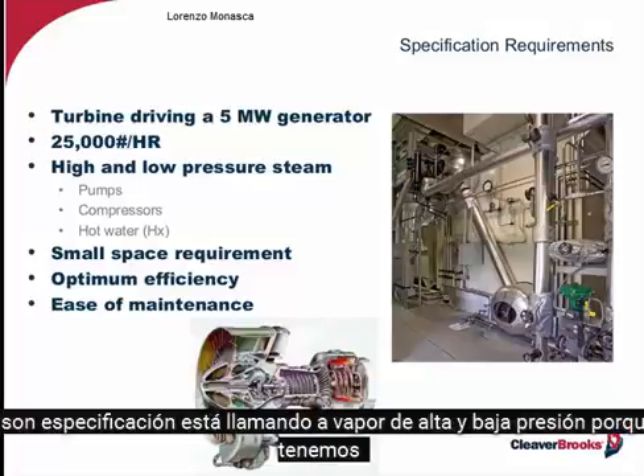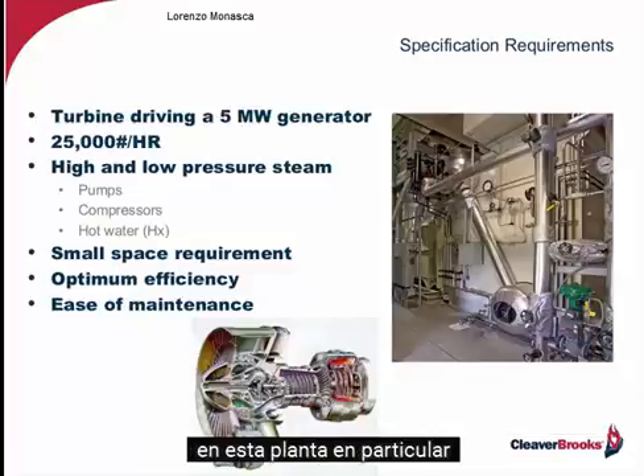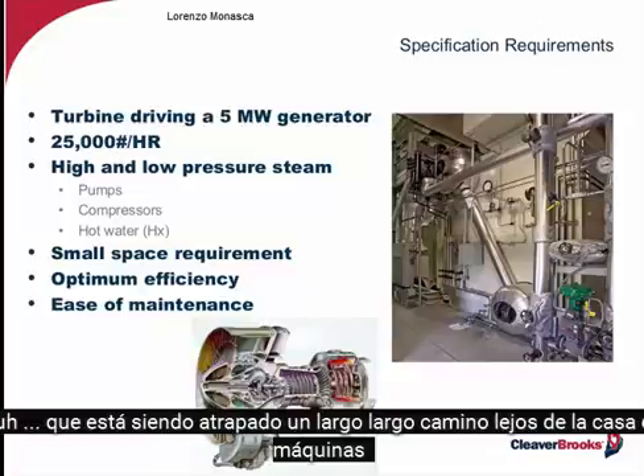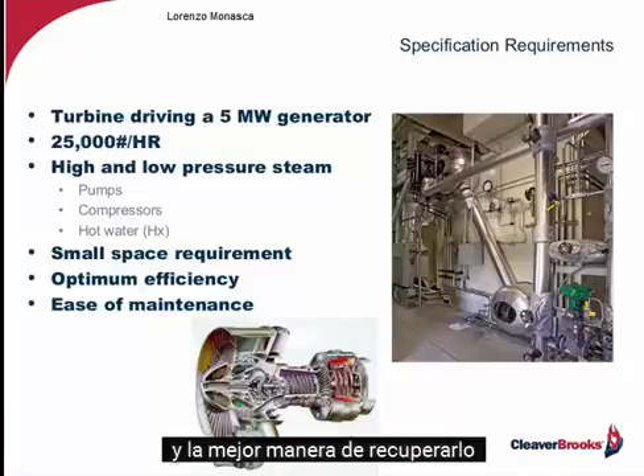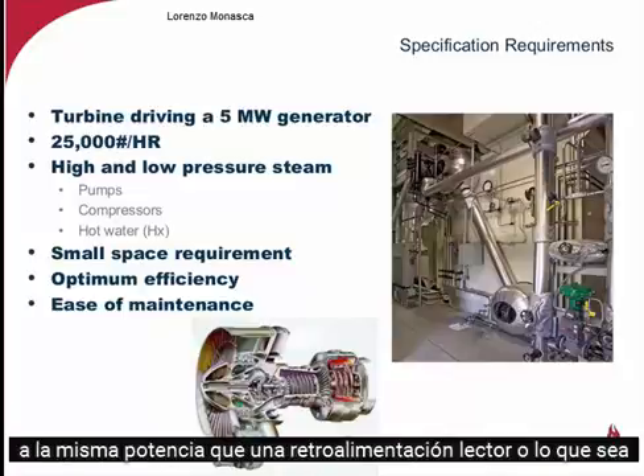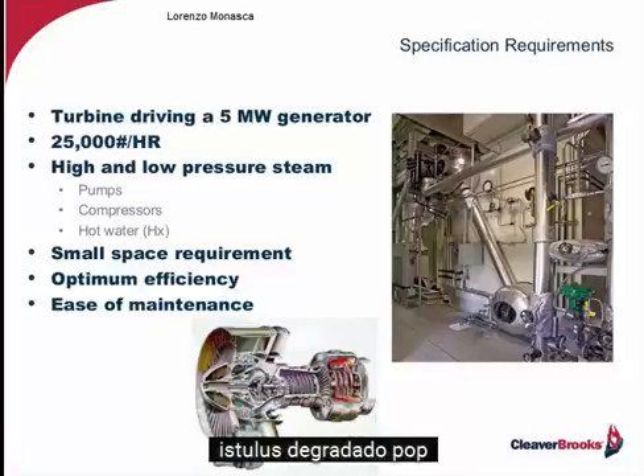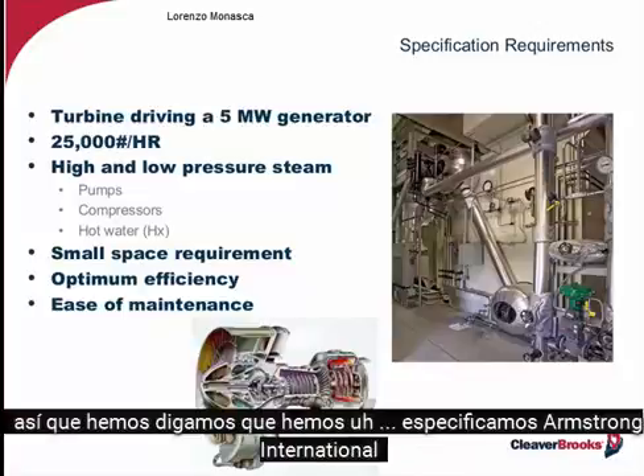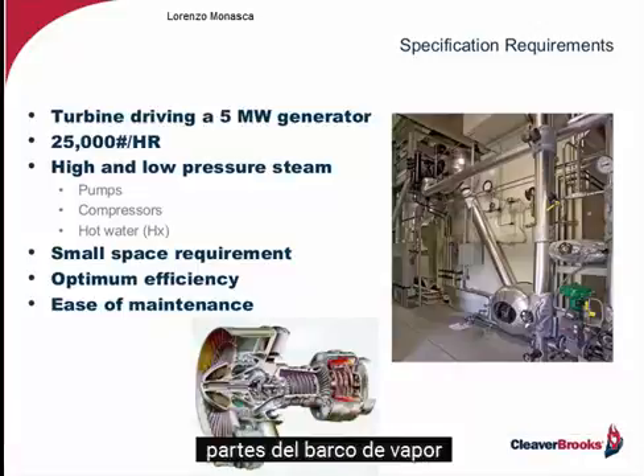Our specification is calling for high and low pressure steam because in this particular plant we have some condensate that's being trapped a long, long way away from the powerhouse. The best way to get it back to the powerhouse itself, to the deaerator or feed tank or whatever, is through a steam motive pump. So let's say we've specified Armstrong International steam motive pumps.